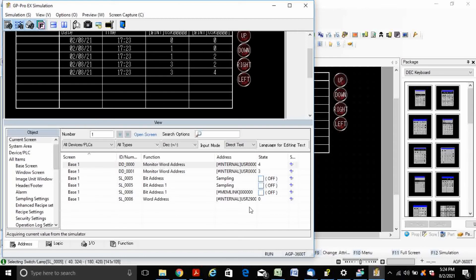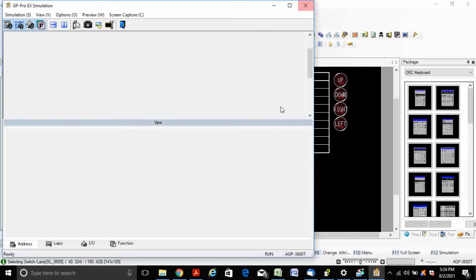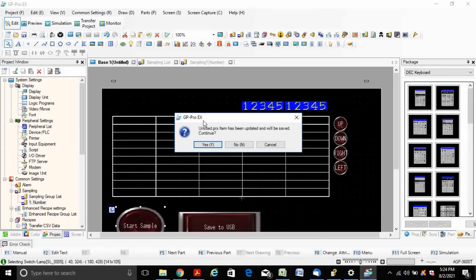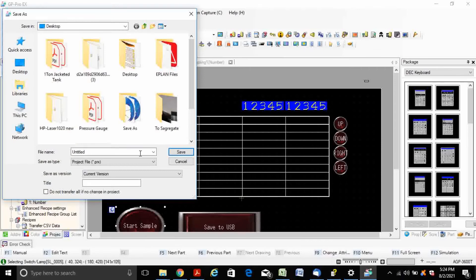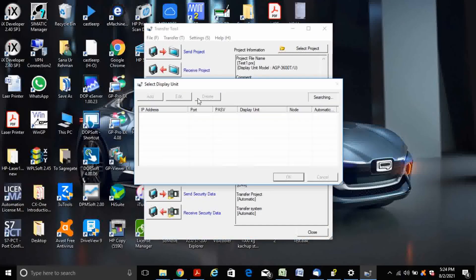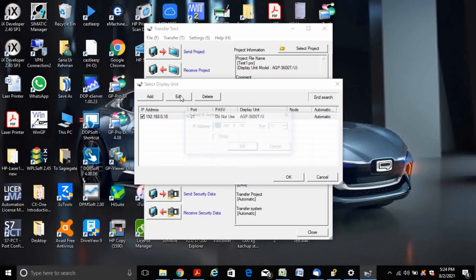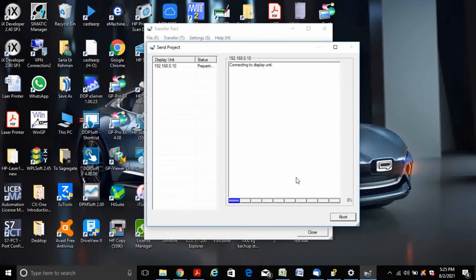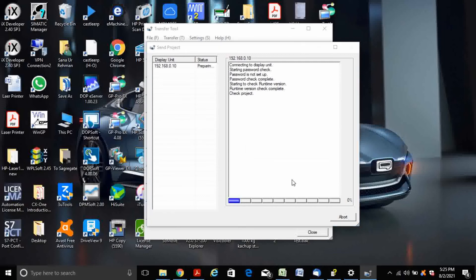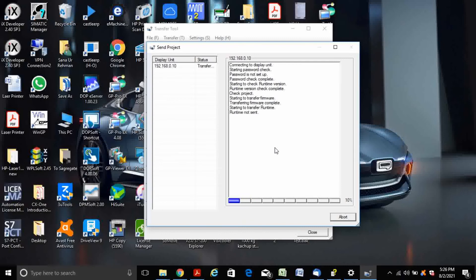Now download this program to the HMI and check whether it's saved in the USB via HMI. Set the file name as test1. Since I have connected the Ethernet, do not use passive mode. The program is currently transferring from PC to HMI.